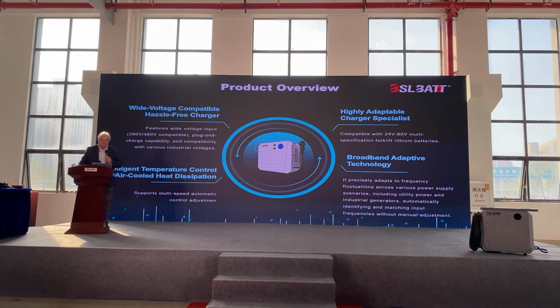Looking at the product overview, it's a wide range of compatibility. Right now we can handle voltages from 380 up to 480 and in between, so depending on your AC input location or country, we're able to handle those voltages. It's got intelligent, controlled air-cooled forced air system with variable cooling, adjusting based on the temperature of the internal components to keep them working in an acceptable range. The DC output for the batteries we're charging can be anywhere from 24 to 80 volts. So 24, 36, 48, or 80 volt equipment can be handled by these chargers. The mix is 24 volt is singular, 36 and 48 is common, and 80 volt is singular—basically three different sets of voltages for the DC output.